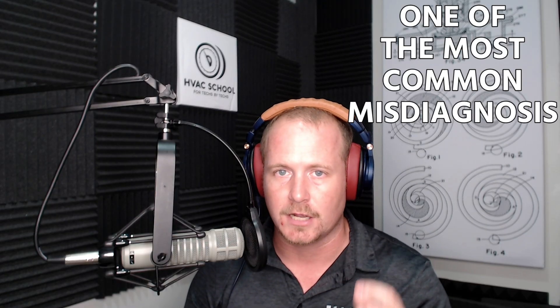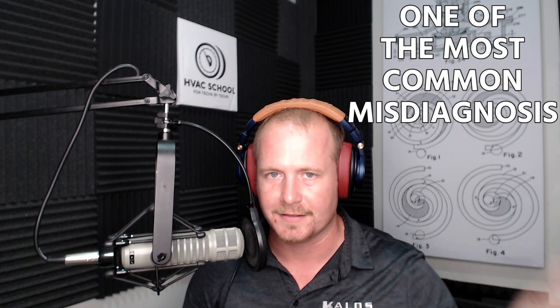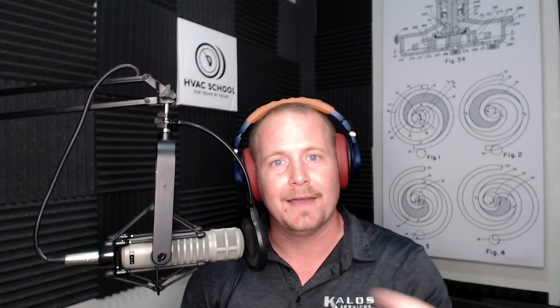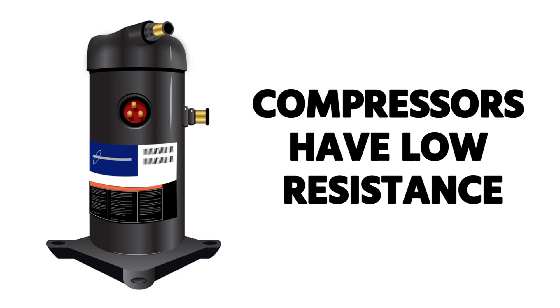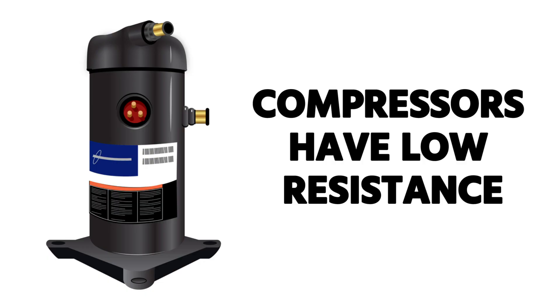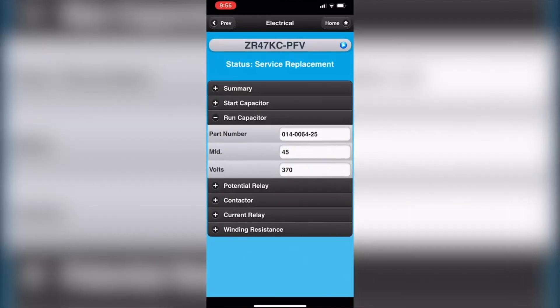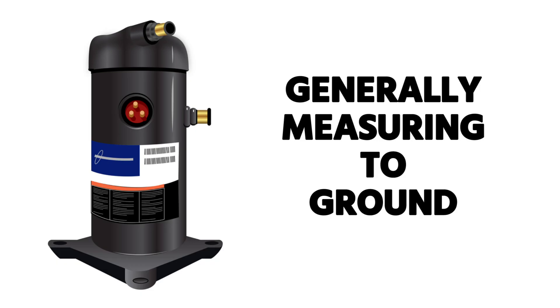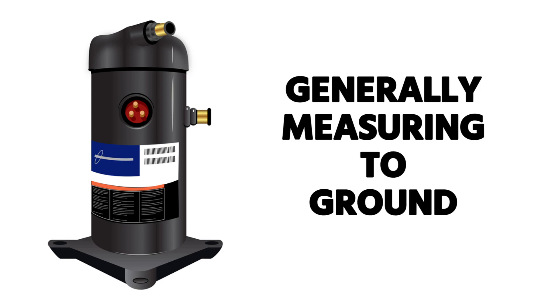And even if you have a leg-to-leg short, it's going to be shorted to ground. The reason I say this is because that's one of the most common misdiagnoses. Technicians go in and they measure with an ohmmeter between the terminals, they see a low resistance on the compressor, and they say it's bad. But compressors have a low resistance just out of the box. If you look at, for example, the Copeland mobile app, you'll see that the resistance measurement from terminal to terminal is actually quite low and it's designed to be. When you're looking for a short circuit on a compressor or a motor, generally you're going to be measuring to ground — and that's where you're going to find that short circuit.